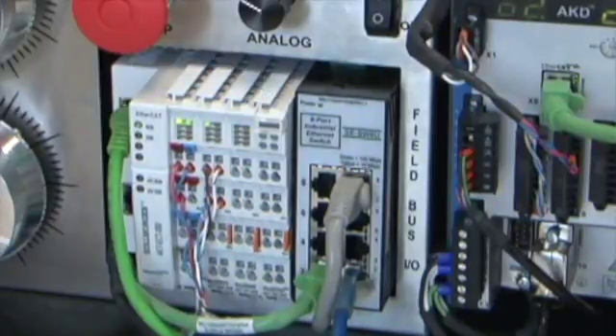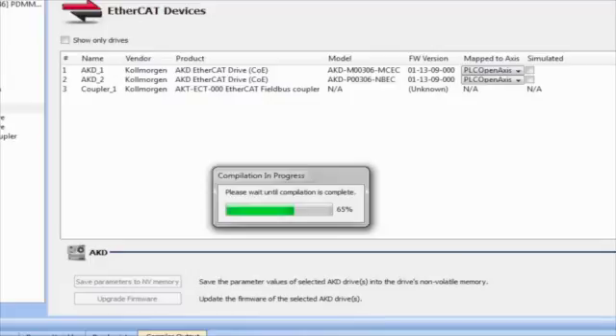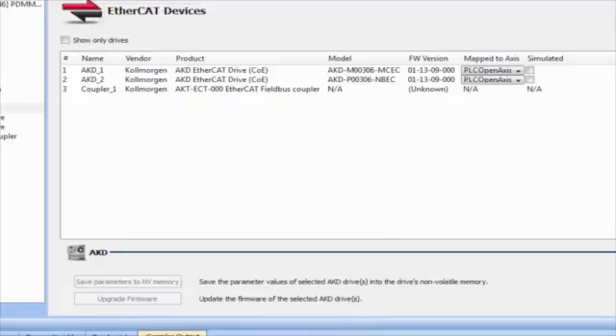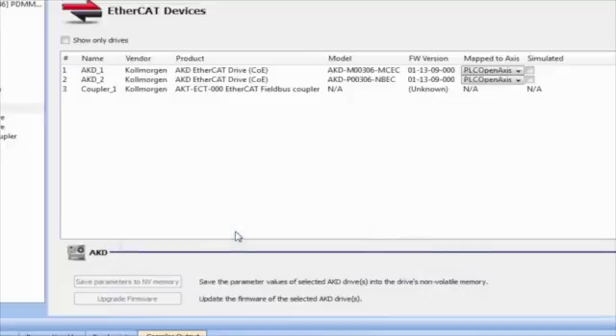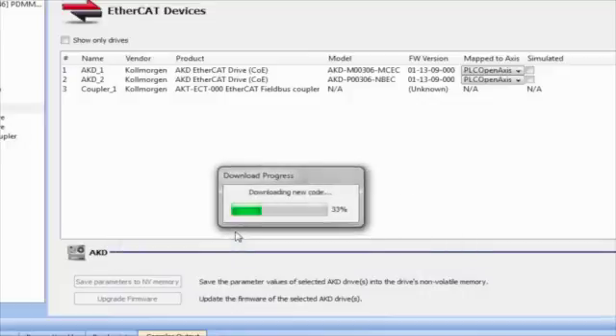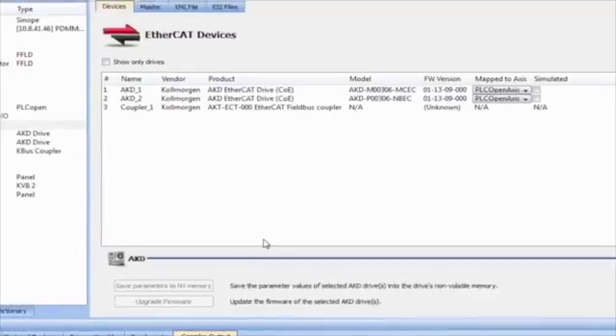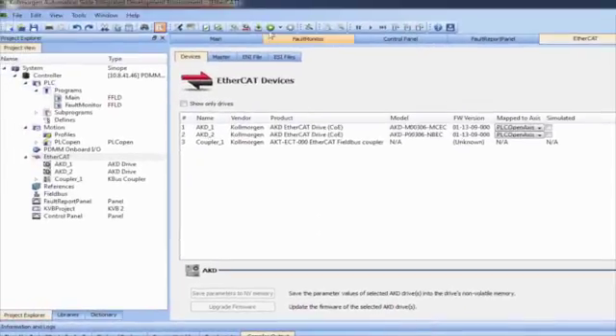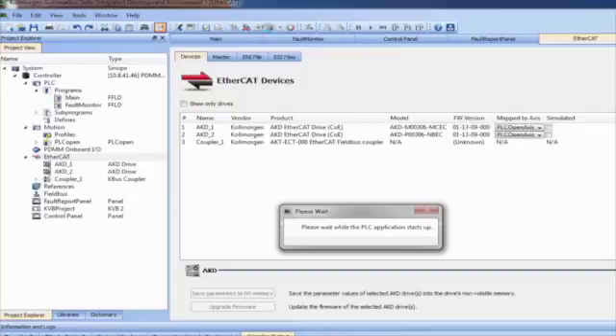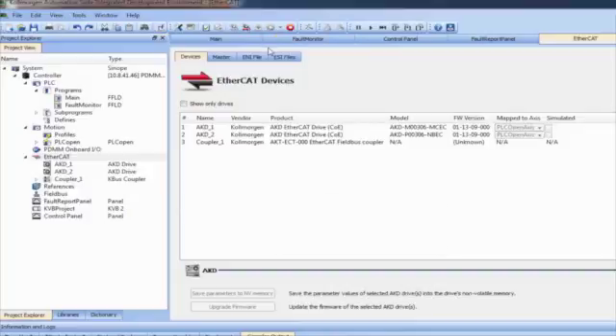After discovering all the components, the project must be compiled to create an EtherCAT configuration file. This will be loaded in the PDMM master when the project is downloaded to the target. Enter the IP address of the PDMM in the Controller Properties window by right-clicking on the controller and then selecting Properties.